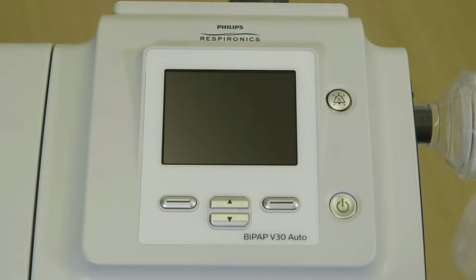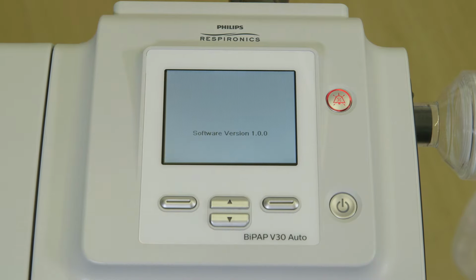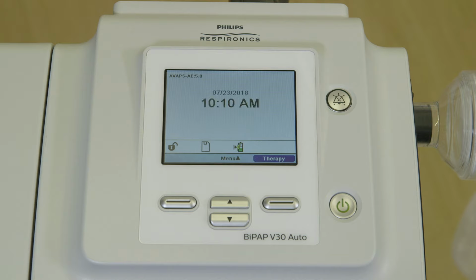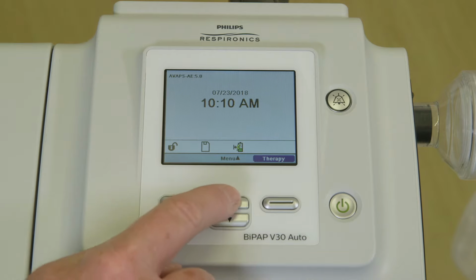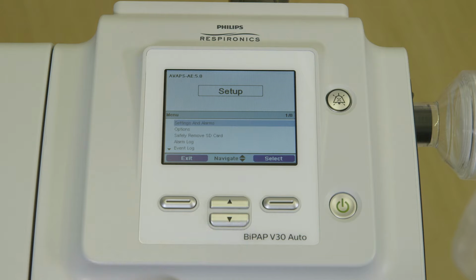Next, to power on the device, select the power button from the front. You will see the main standby screen, which includes the time and date, current mode, and soft keys used to enter the menu and begin therapy. For ease of operation, there are only two menu layers to navigate. To set up the V30, select Menu from the standby screen using the up arrow and then choose the topic. You can now adjust any and all relevant settings and options.